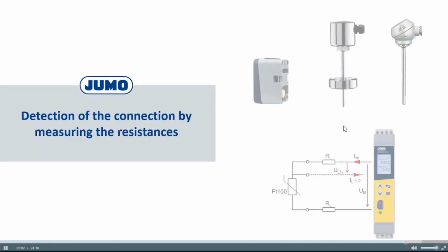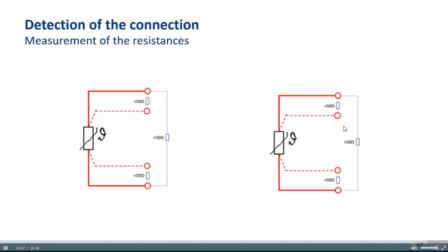And then finally, I have a little practical tip here. Maybe you find somewhere a probe with many wires, or you have a lot of connectors in your head. You have no idea what this is. Is this a 3 wire, 2 times 3 wire, 4 times 2 wire, something like this? How to find it out? If you have an ohmmeter, then you can do it as follows. You can always expect an RTD temperature probe in 4-wire technology at first.